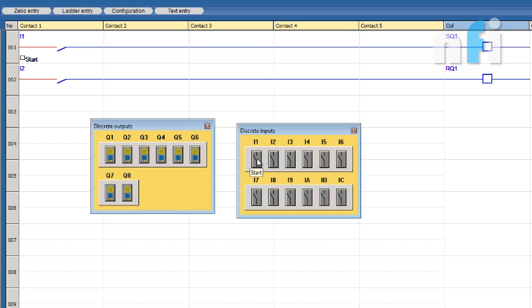But if you work on Allen Bradley, there are two types of set reset, RS and SR. If you're using the RS type set reset command, reset is dominant. If you're using SR, set is dominant. But here you have reset which is dominant. So this is called simple latching and unlatching.